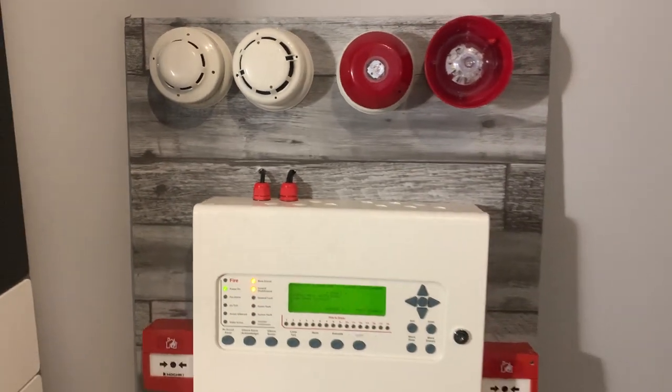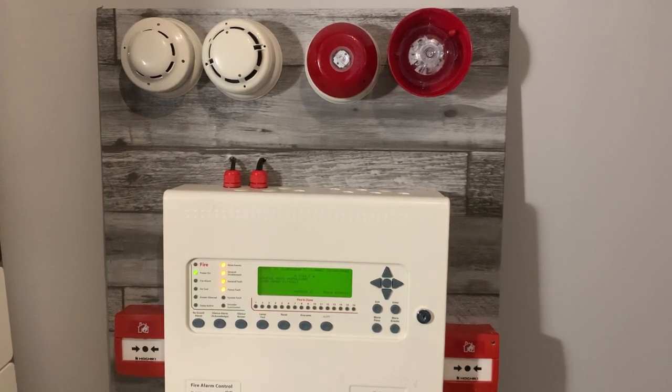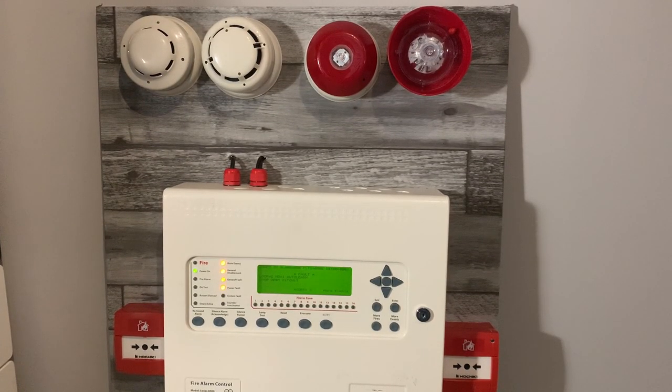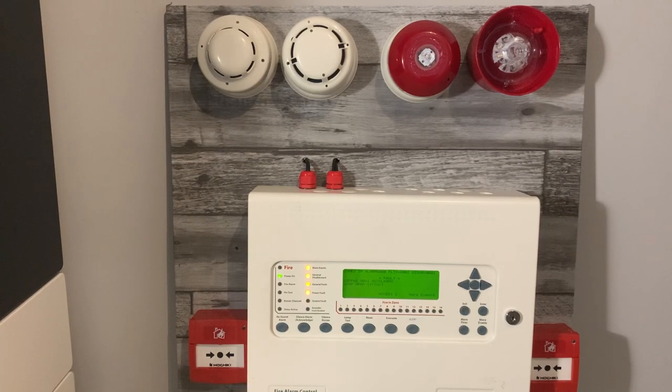If we go to the bottom, on either side of the panel we've got two Hochiki MCPs, and both of them don't seem to poll — I'm not sure why — but that's fine. Same Kentec panel, so I'm not sure why the Hochiki call points aren't polling. They were when I first set them up, which was really weird.